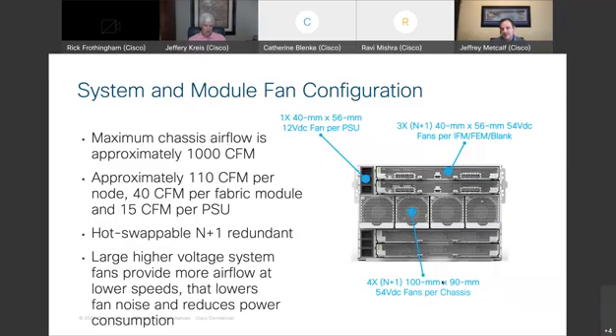So the takeaway here is just the sheer amount of airflow. This chassis is designed for 10 years and beyond. We've over-provisioned the volumetric airflow capability of the system fans to support air cooling into the future, with 1,000 CFM. By no means at first launch are we going to require 1,000 CFM to cool any type of solution based on Ice Lake. Again, this is built for 10 years.